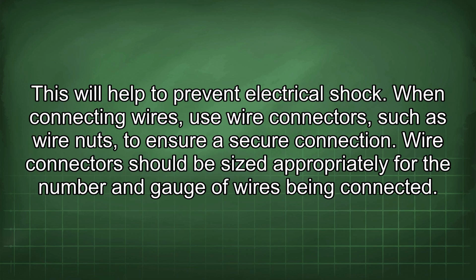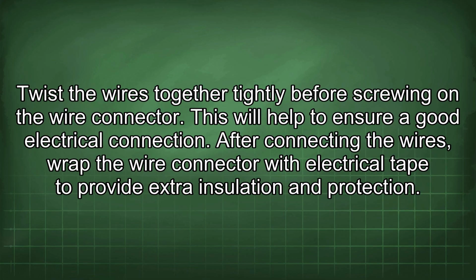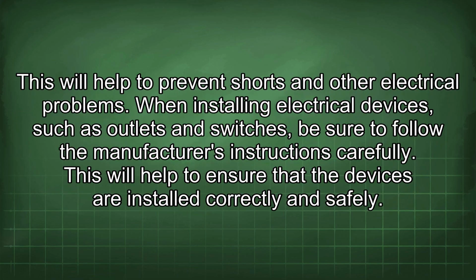When connecting wires, use wire connectors, such as wire nuts, to ensure a secure connection. Wire connectors should be sized appropriately for the number and gauge of wires being connected. Twist the wires together tightly before screwing on the wire connector. This will help to ensure a good electrical connection. After connecting the wires, wrap the wire connector with electrical tape to provide extra insulation and protection. This will help to prevent shorts and other electrical problems.